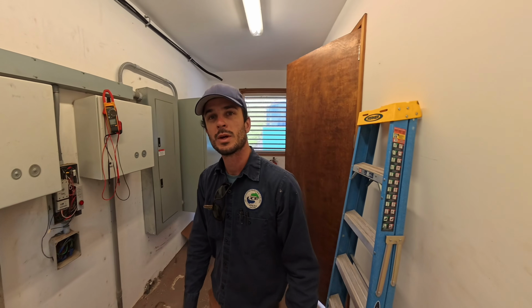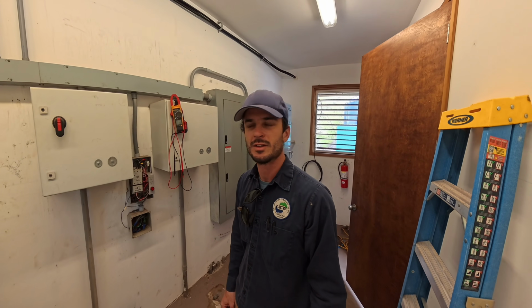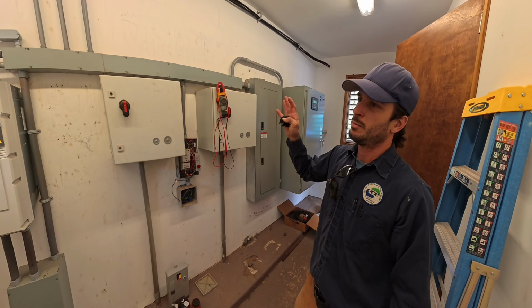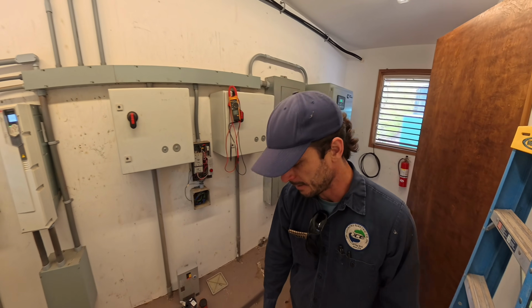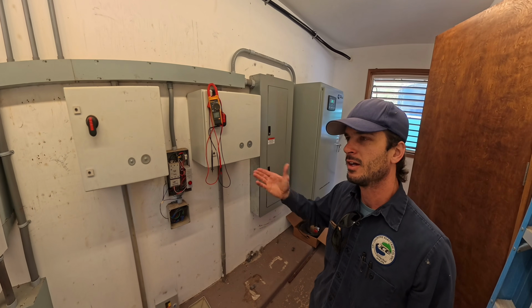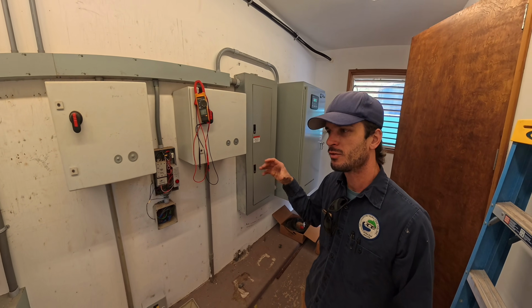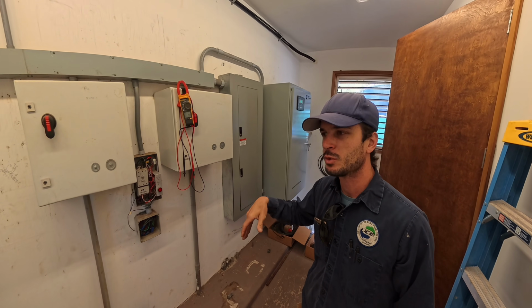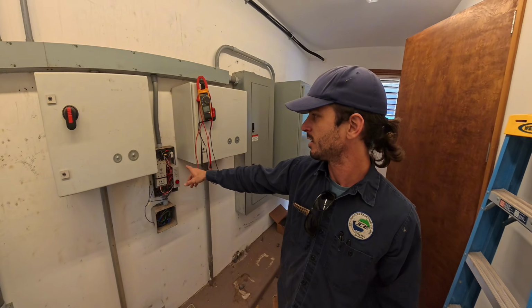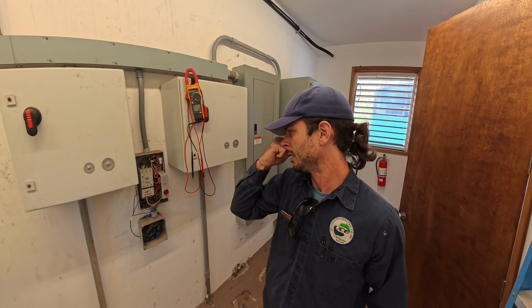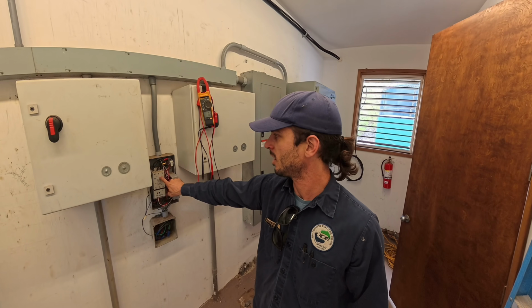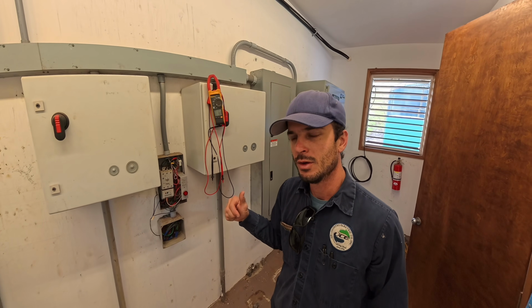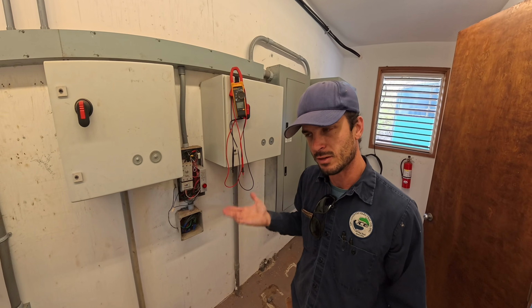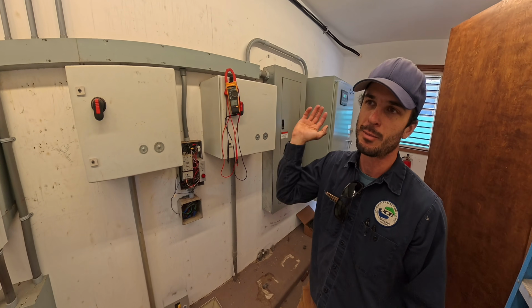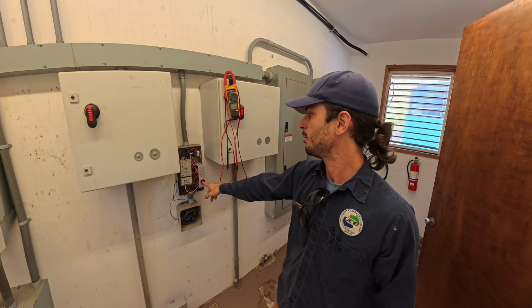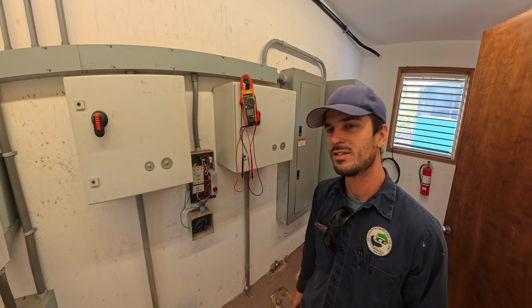Hey guys, we got a little bit of wiring to do today. Customer's modifying their pump system, and they currently are sucking water out of a small trough. They have a float switch in there, but the float switch is in series with the direct run logic here, hardwired into the coil logic of this contactor. And so in the event that the water in the trough gets low and that float switch opens, they have to send an operator way out here to manually hit this low-level reset push button here.